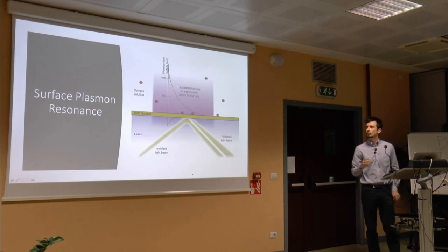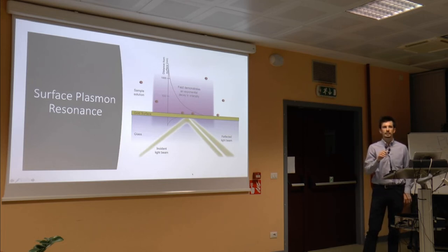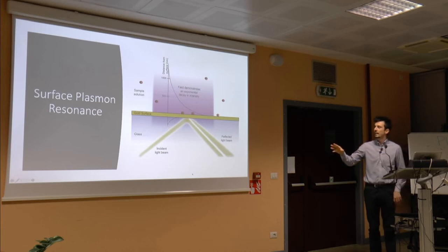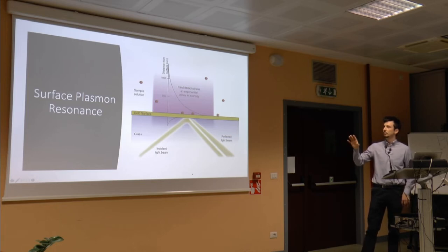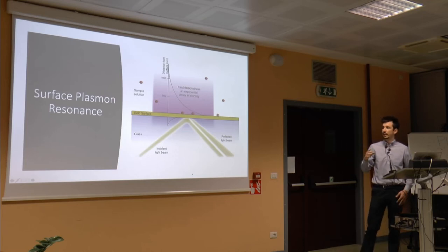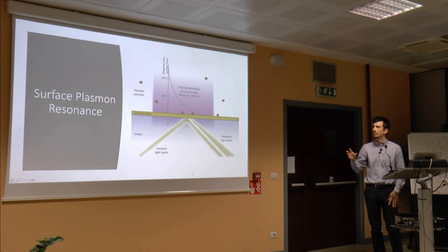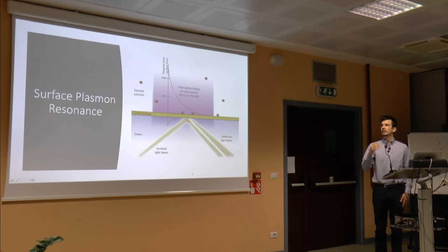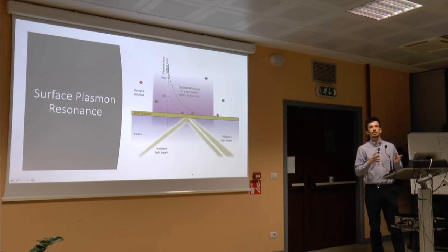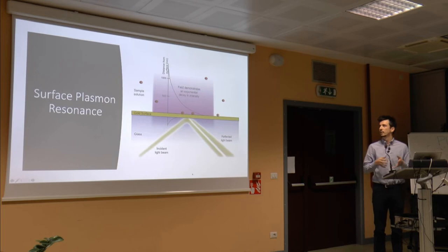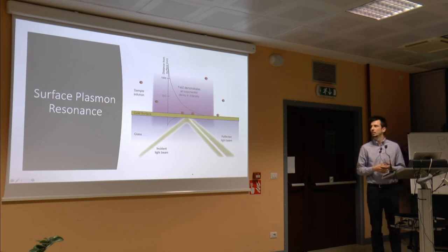Which phenomenon have we selected to sense the refractive index? There are many ways, but I will talk about surface plasmon resonance. A glass substrate has a gold surface on one side. In any ordinary case, when light hits a metal interface, the biggest part gets reflected back, while light also penetrates a little depth into the metal, exciting electrons which oscillate and absorb some energy as heat. So a large part is reflected and a smaller part is absorbed and converted into heat.